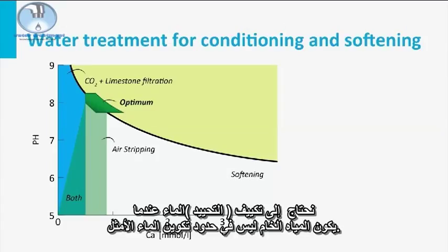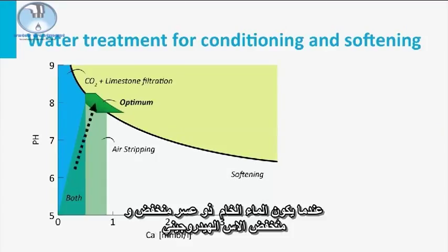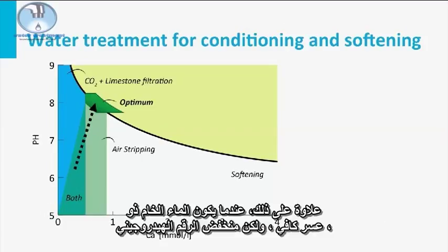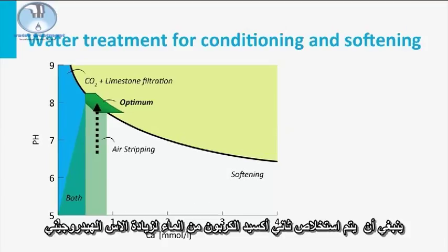Conditioning of the water is needed when the raw water isn't in the range of optimal water composition. When the raw water has a low hardness and low pH, it should be passed through a calcium carbonate filter to dissolve calcium and bicarbonate as well as to increase the pH. When the raw water has a sufficient hardness but a low pH, carbon dioxide should be stripped out of the water to increase the pH.